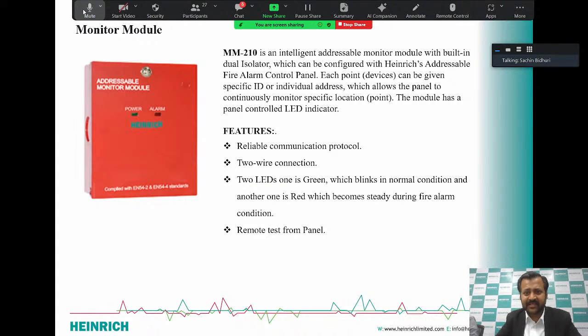So this is the monitor module. As you can see, it has built-in dual isolators, and it is connected to the fire alarm control panel. It has the same features: a reliable communication protocol, two-wire connections, and LEDs, both green and red. Remote test panel: you can have a remote test from the panel itself. These are all connected in the loop. There is no requirement of extra or different power supply for these modules.